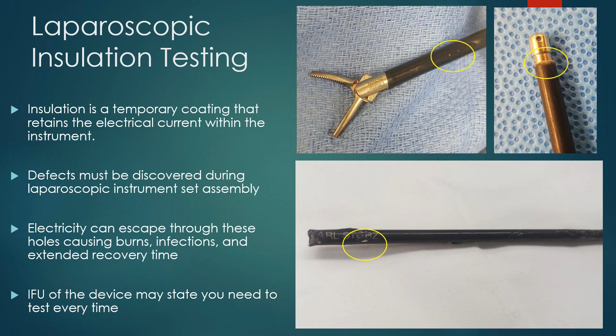The IFU of the device may state you need to test every time, and examples of the IFUs for insulated devices we're actually going to go over on the next few slides, because I thought it was important to see what the IFUs are saying out there now. So some examples of IFUs, I chose a handful, and the first one I picked was Spectrum laparoscopic instrumentation. What's really interesting, it says in here, important note, at this point in the process, Spectrum recommends testing the insulation for cracks, gaps, where the shaft meets the tip at the assembly, and of course pinholes.